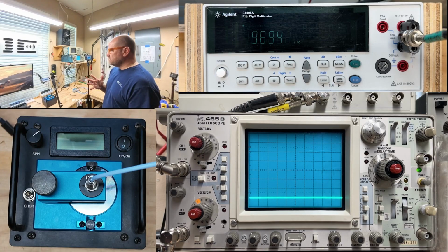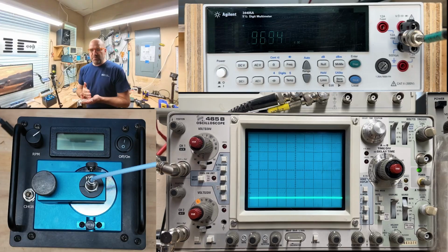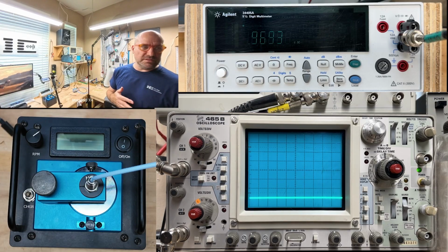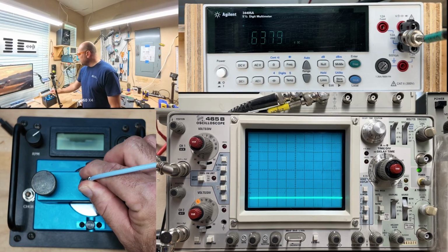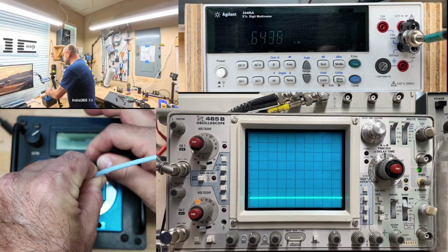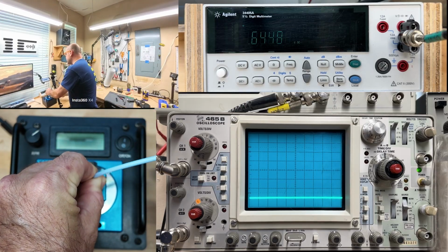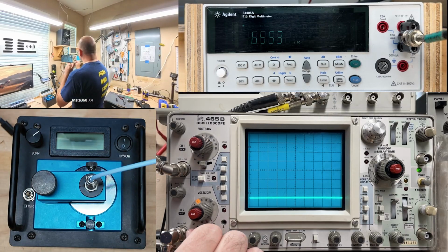To simplify things, I inverted the polarity of the probe. The proximitor is going to spit out usually a negative voltage, but I flipped that around so that we're dealing with positive voltages. So the first thing about the proximitor is the output voltage is directly proportional to the distance, or the gap between the probe tip and the target. Here I am pushing the probe against the target, and you can see that the output voltage is 0.644 volts, or 644 millivolts. We're basically on the ground.